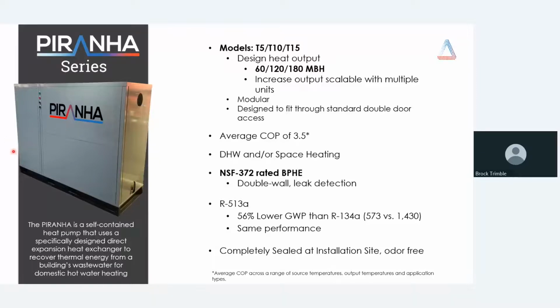So this Piranha is available in three sizes, the T5, T10, and T15, and they each have their nominal design heat output that you can see here, 60, 120, and 180 MBH. So that's MBH is 1,000 BTUs per hour. So 60,000, 120,000, and 180,000 BTUs per hour output. Now, these units, very much like any other boiler or heat pump that you might be familiar with, are able to be installed in parallel, multiple units running side by side, in order to increase the overall energy recovery and energy output capacity that we have for the system.